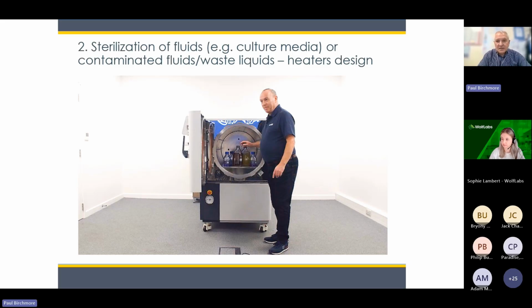The advantage is the dry system can be significantly quicker for the cycle. With a media load, a lot of time is taken for cooling down at the end of the cycle after the sterilization part of the process. And with the enhancements, you can speed up that cooling part of the cycle. So for some labs who have a high throughput of bottled media and they really need to optimize the process, then adding those extra features would enhance the cycle time overall, over one load and over a number of loads during the day. Obviously, it's not insignificant, those extra features, and they could add significantly to the overall budget required for that product, as much as 30% perhaps. So you don't do it lightly unless you need to justify it, unless the cost balance equation works out in favor of higher productivity.